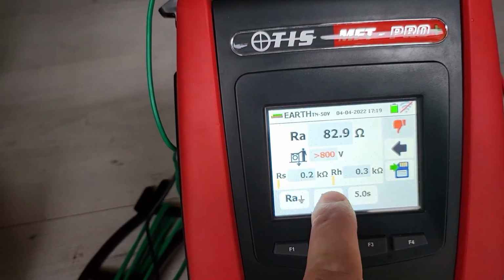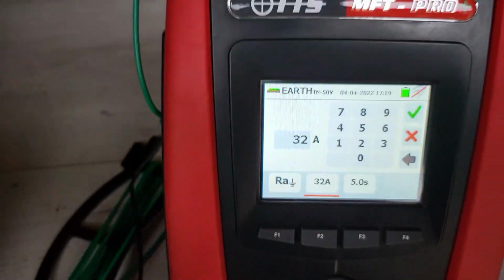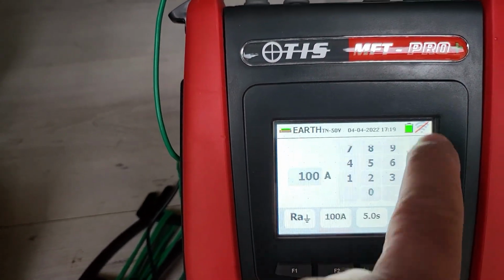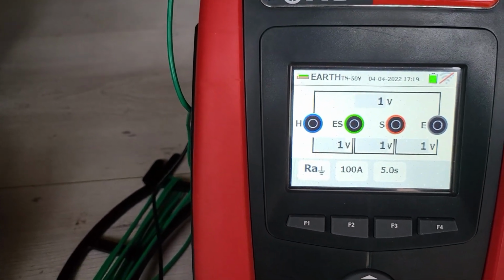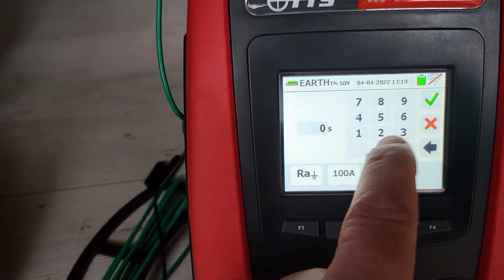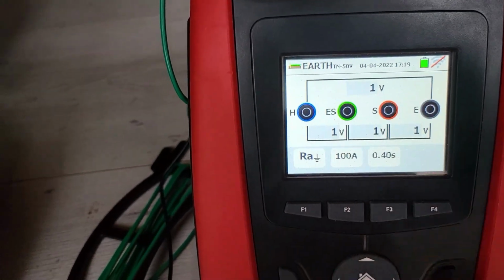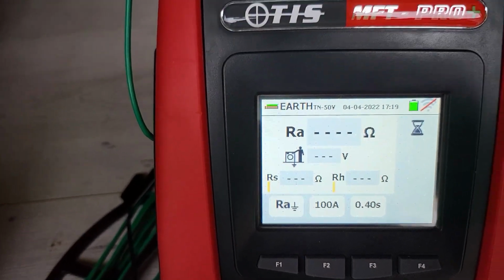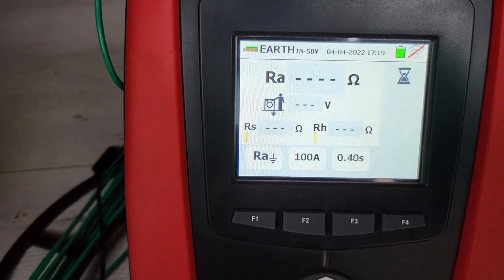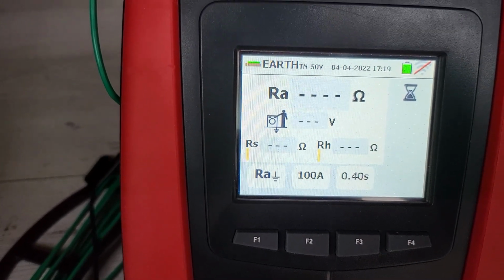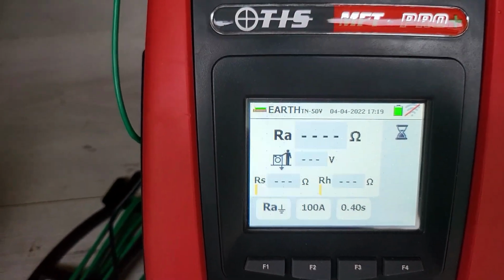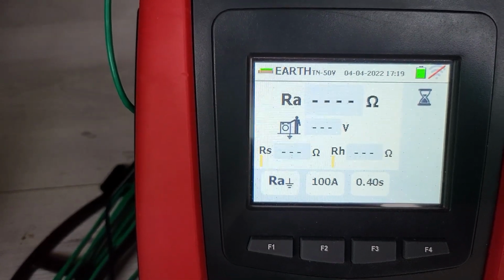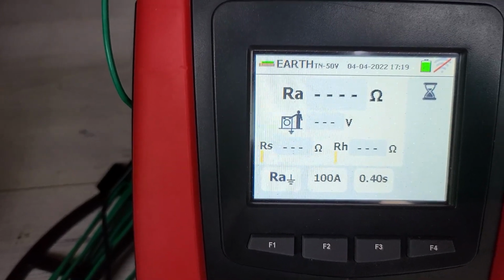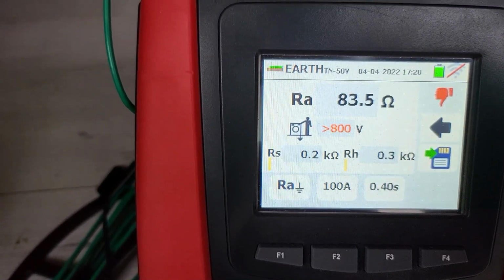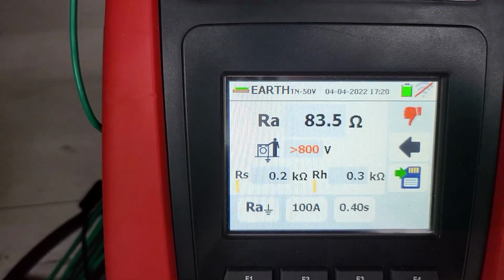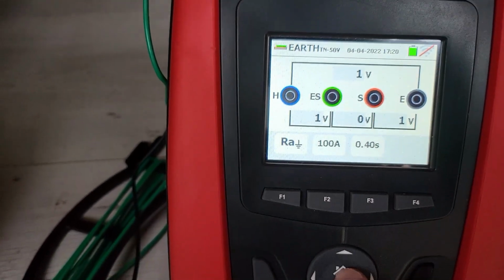So that's those ones. If I am to play around with this, and if we were imagining this was a TT, for example, with a 100 amp head as a typical example, and we want to be on 0.4, this is just to demonstrate the different calculation that the test set actually makes for you when you're processing the test. And you can see here I've actually got it set in the TN mode, so we'll adjust this as well. So again, it's having a good old think, measured a similar value, and it's given us another thumbs down because it thinks we are on a TN system.